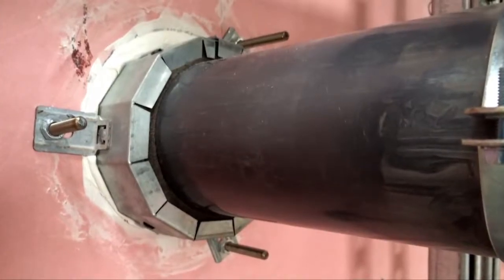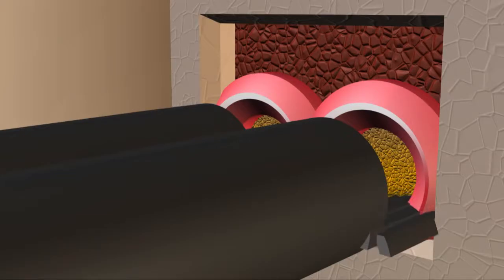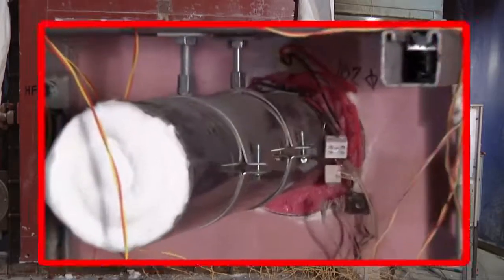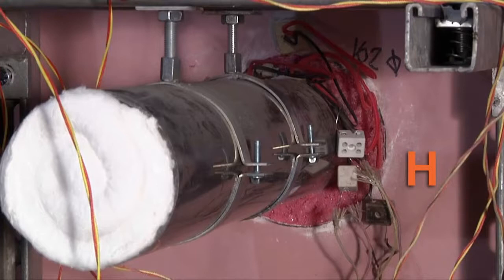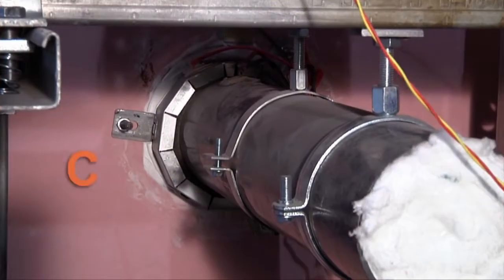Plastic pipes: In the case of plastic pipes, it is essential that the fire-sealing system closes down the opening through the pipe as it melts. H shows a foam inappropriately used to fire-stop around a plastic pipe with no means of closing the opening. C shows an identical plastic pipe protected with a correctly installed fire-resisting intumescent fire-stop pipe collar.